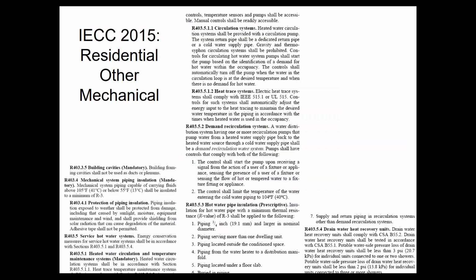All right, last thing on residential, there are several other requirements. I will point a couple of them out here. One, you cannot use the building cavity as a ducting system. That used to be fairly common. You would use a return duct, you put some panning on the bottom of your joist to your basement, and that would be the bottom of your 4-sided duct, if you will. 2x4s would be the sides, and the plywood on top would be the top. That's not allowed anymore. You have to have a fully ducted system.